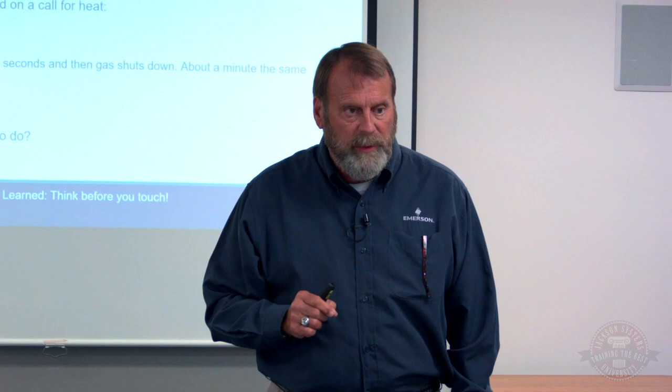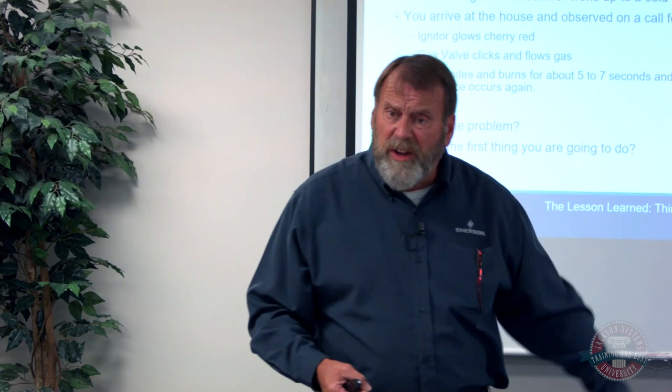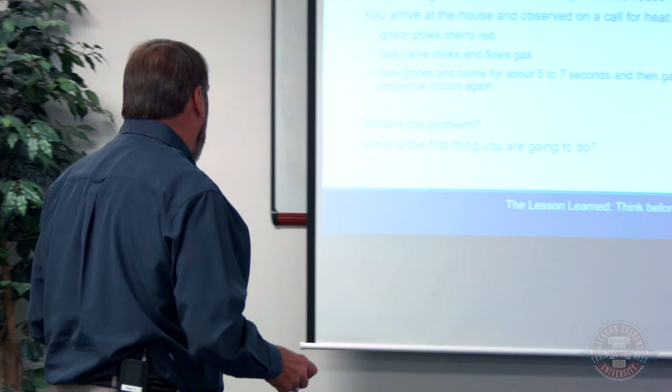As soon as you go in on that second call, the first thing I did was I cleaned the probe, and I moved all the wires out of the way to get that probe out of there. As soon as you start moving wires around, especially if one of them's the ground wire, you move it enough, it's going to make firm contact again. Let's go through the circuit and understand how these things work.